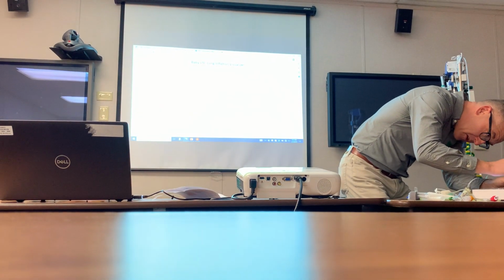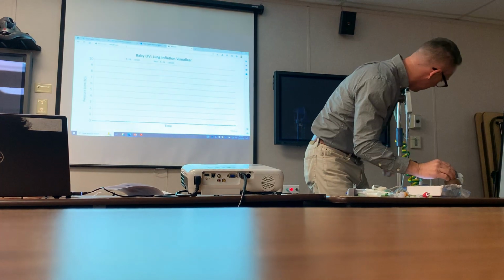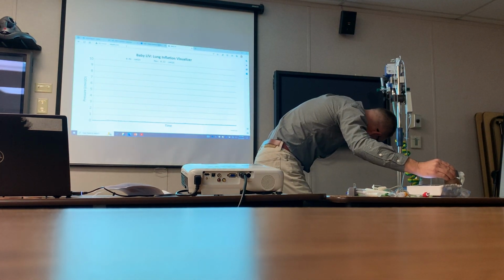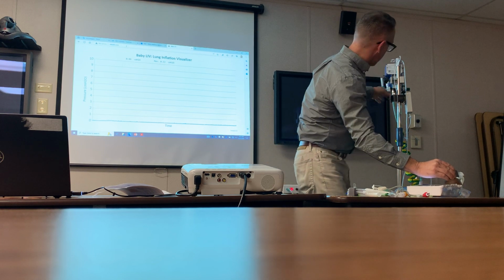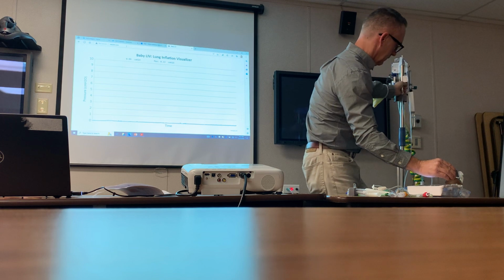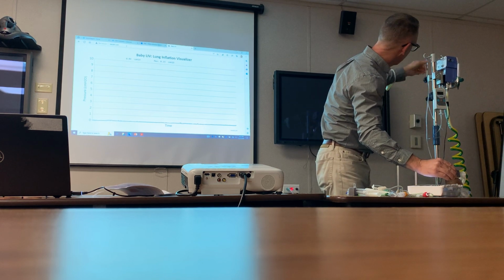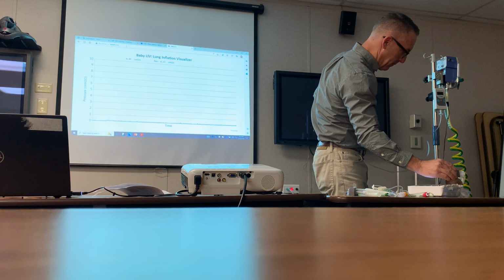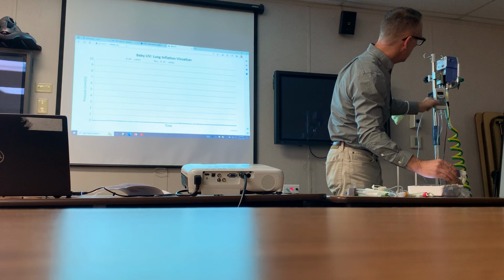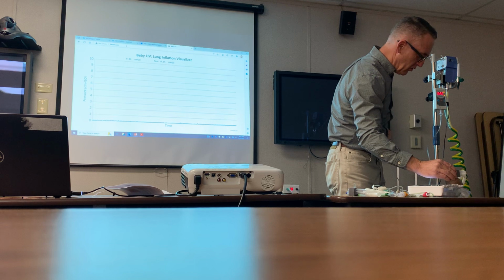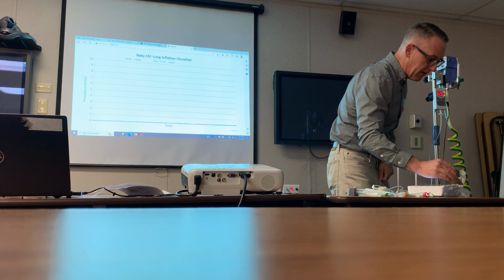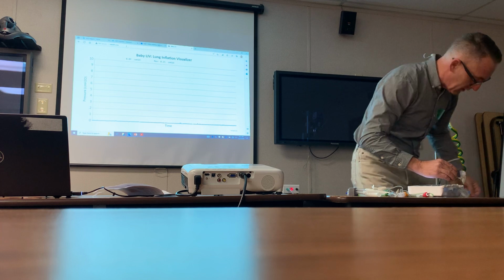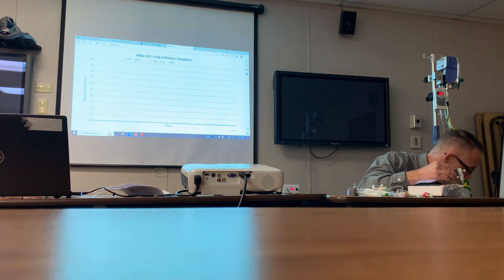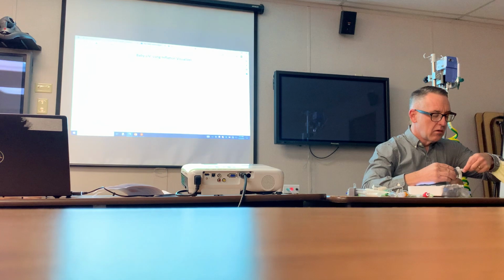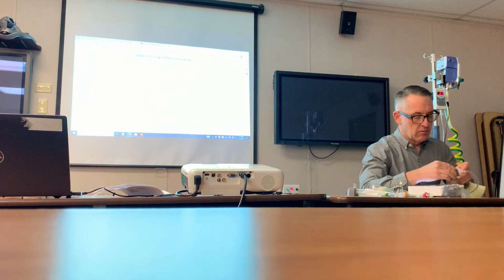So I've got 100% occlusion of the nares. The pacifier that you see here is going to represent mouth leak. Now if you look at this, I'm going to have it set at 5 centimeters of water pressure. This here is a bubble CPAP manometer from DRW. Bubble CPAPs typically don't use manometers, but they're becoming more and more popular because this one comes with an alarm that allows you to determine if the pressure is too low or too high, whether you have a leak or not.